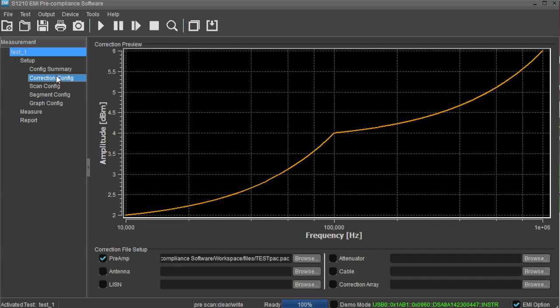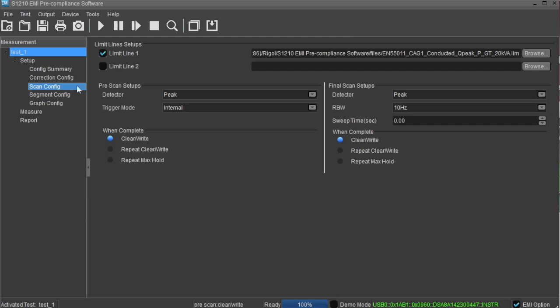The correction config area displays the correction factors that are currently applied to the instrument. The available corrections can be tied to separate preamp, antenna, LISN, attenuator, cable, and correction array files. The scan config area contains 2 limit line selections, pre-scan detector and trigger modes, and trigger types. It also contains the final scan settings for the detector resolution bandwidth and trigger types.